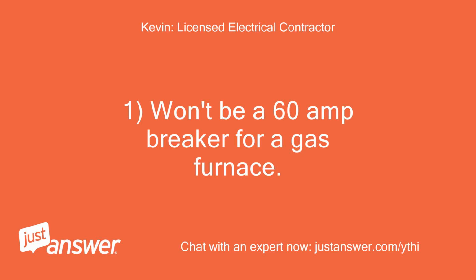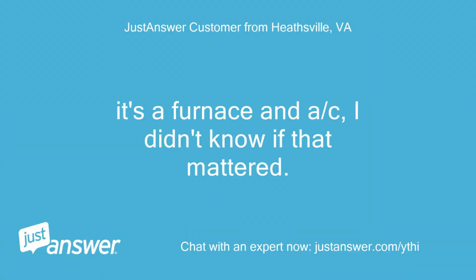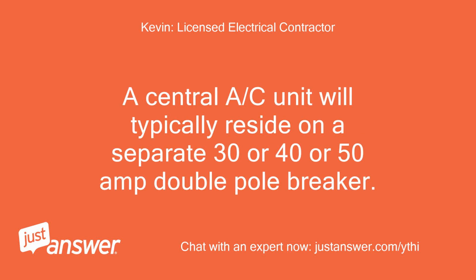1. Won't be a 60 amp breaker for a gas furnace. Will either be a 15 or 20 amp single pole breaker. It's a furnace and AC, I didn't know if that mattered. 1. The gas furnace will reside on either a 15 or a 20 amp single pole breaker. A central AC unit will typically reside on a separate 30, 40 or 50 amp double pole breaker.